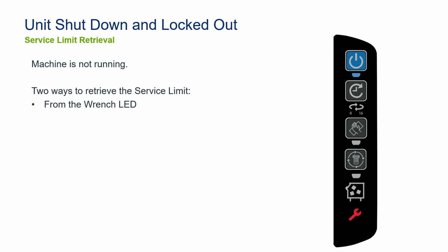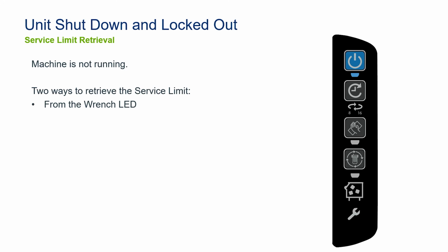Well, there's two ways to do it. You can either retrieve it from the user interface touchpad, or you could retrieve it from the board, but we're going to start with the touchpad. So press that power button, and then you'll see the light flash one time and go out. That'll let you know service limit number 1 is what shut this ice machine down. If it flashed twice, that'd be service limit 2. If it flashed 3 times, that would be service limit 3. But today we're talking about service limit number 1.